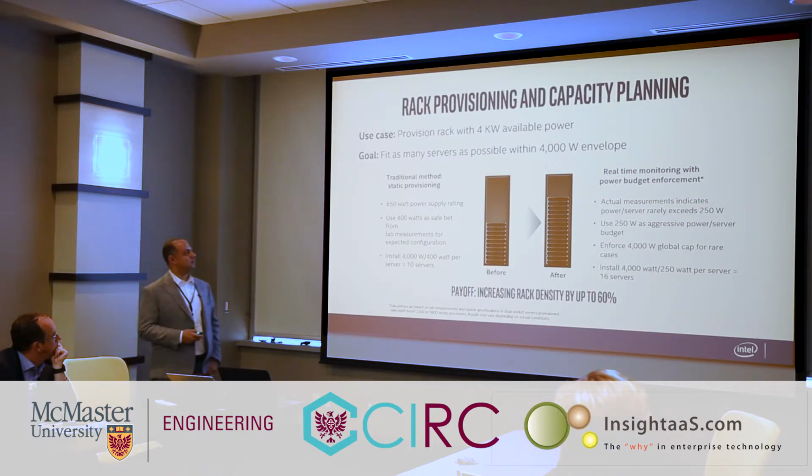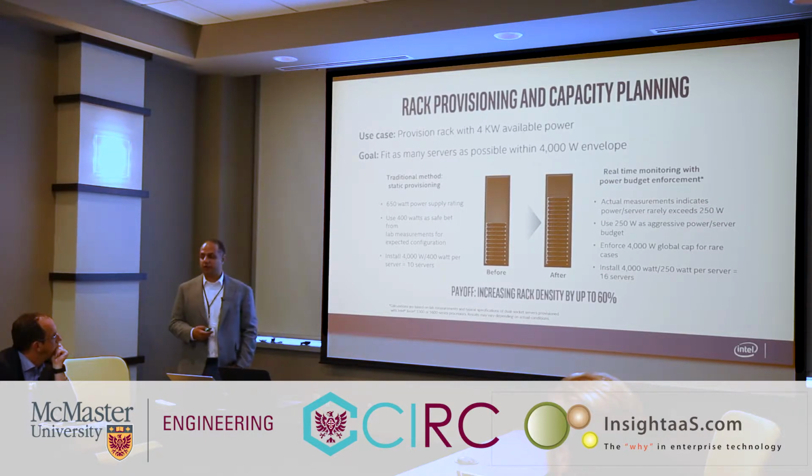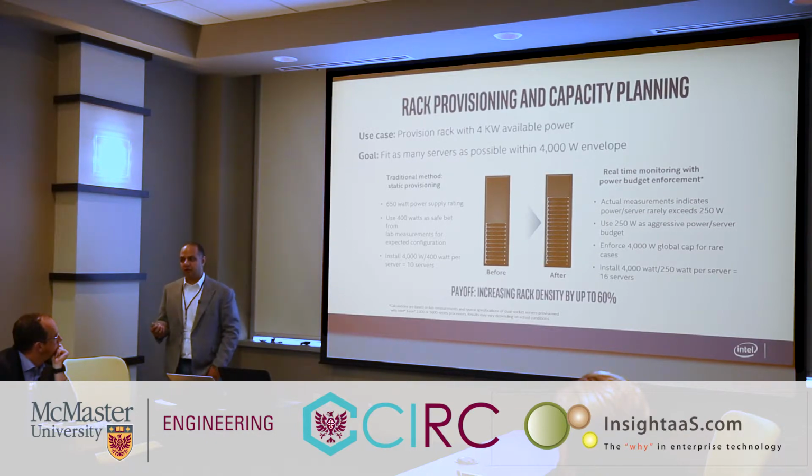Okay, and then this is probably another one, which I touched on already before: being able to increase your rack densities by not depending on the derated power of those servers. Most servers are rated at 400 watts, which typically means maybe 16 nodes per rack. But if your systems only consume 200 watts during the entire year, then you could potentially add 20 to 25% more servers in that rack, and then you don't have to worry about where my next servers should go, I need more space, find a new spot, and so on.